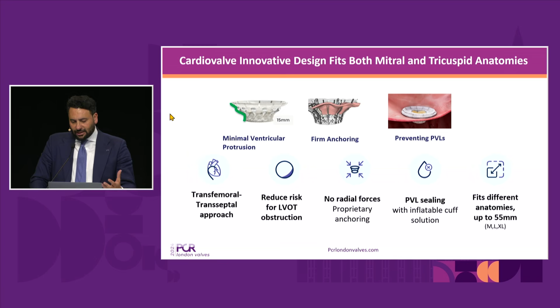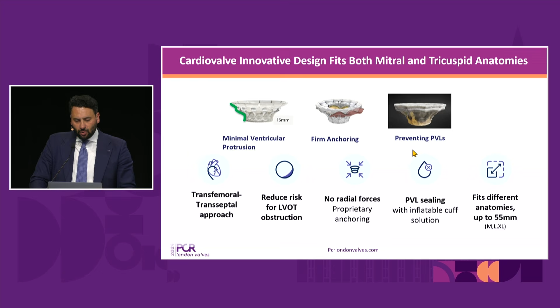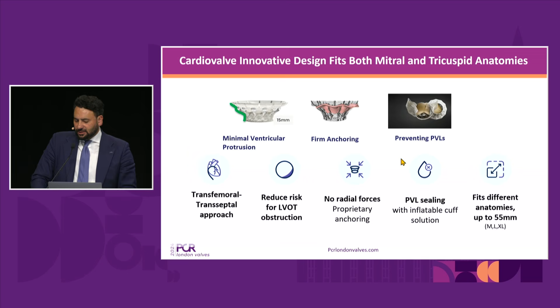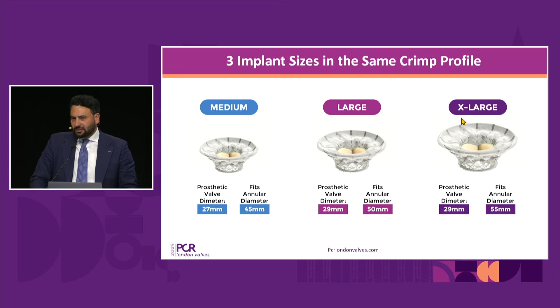So the solution we bring in this symposium for those patients not amenable to TEER is Cardiovalve. It is a very innovative valve design with minimal ventricular protrusion. It has firm anchoring based on a sandwich of the leaflets and the annulus, and a special mechanism for preventing PVL, an inflatable cuff created with the Dacron between the two frames of the valve. It has no radial forces and fits a wide range of anatomies. We have three sizes from medium to extra large, fitting annulus up to 55 millimeters.